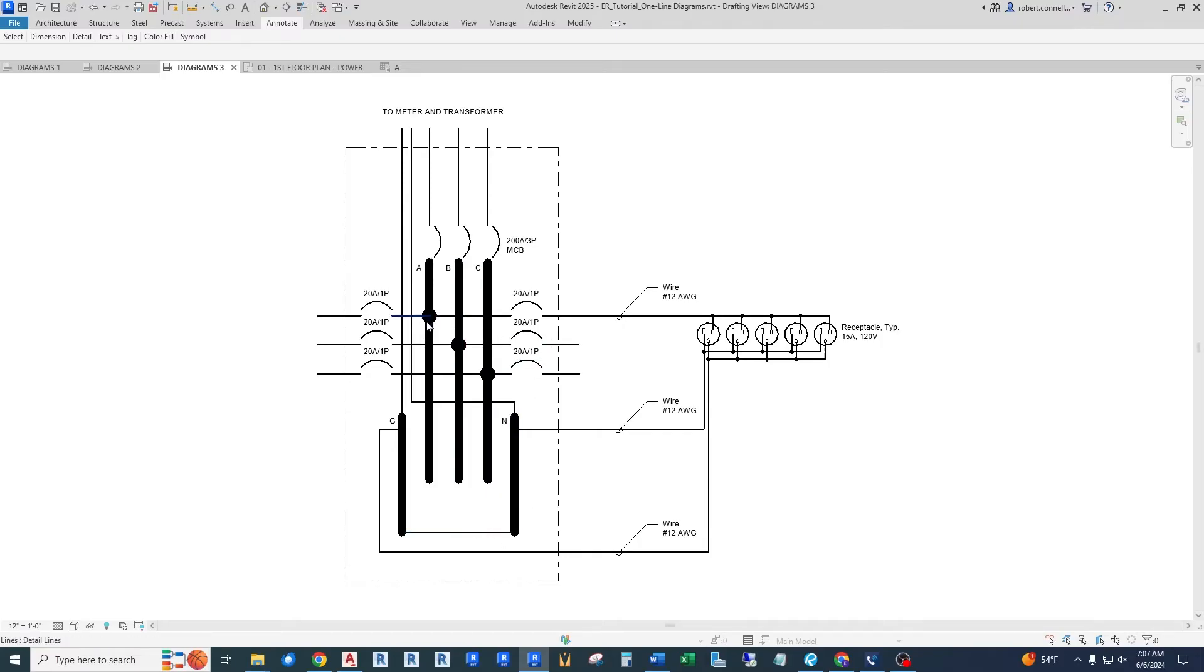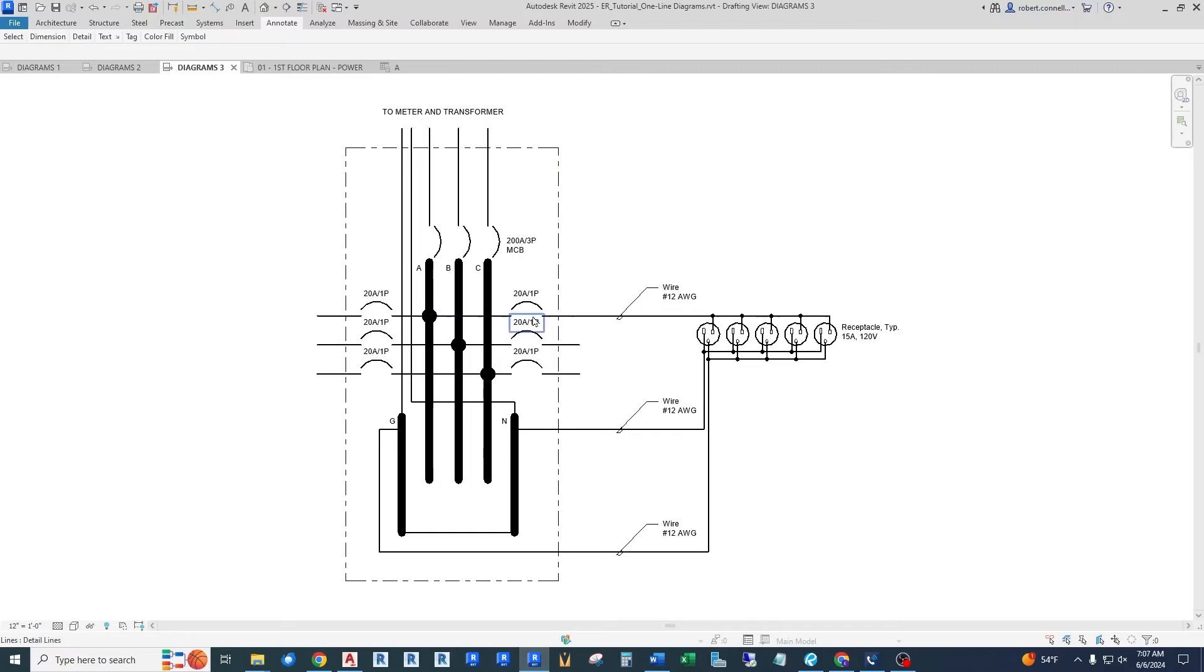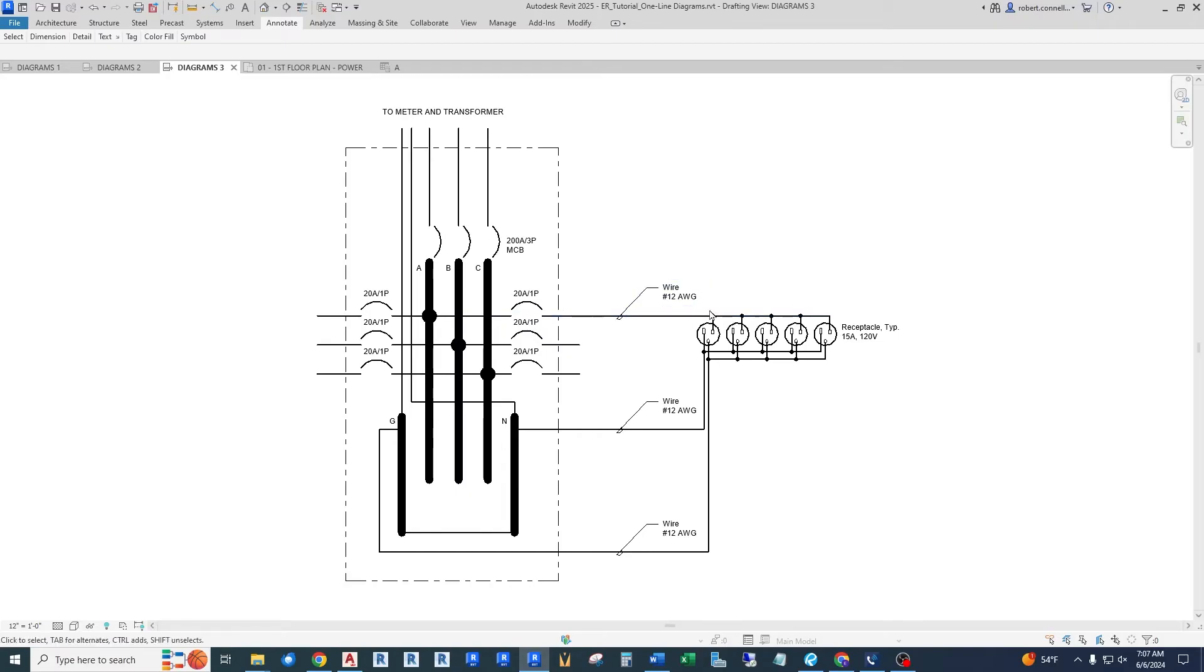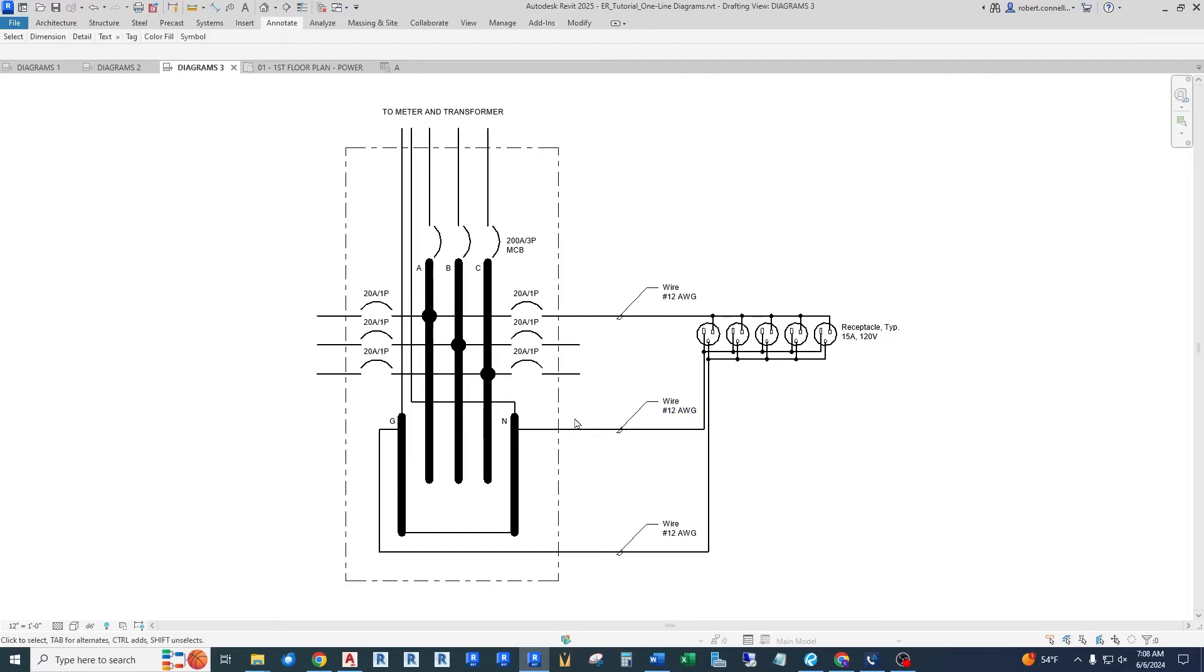And then tapping off of each of these phase bus bars are circuit breakers. One goes off to the left, one goes off to the right, and then phase B, same thing. And I've only shown one circuit, a 20 amp single pole circuit breaker with number 12 wires feeding in parallel five receptacles. So we have the wires all in parallel. These are cables going out to all the wires. And we have the neutral wire here, and we have the ground wire here. This gets complicated and takes up some real estate on this view. And it's just a single circuit.